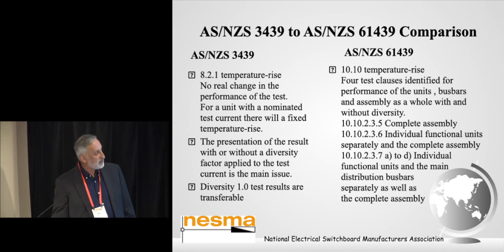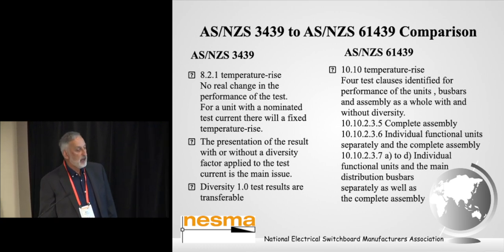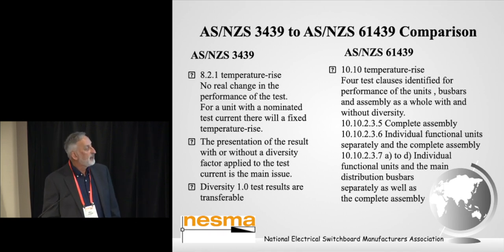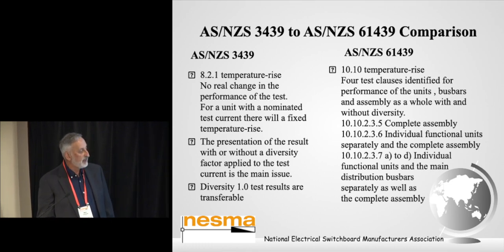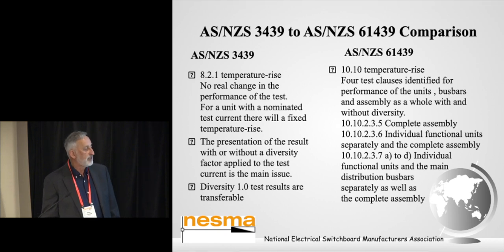But the complication here comes with clause 10.10 for temperature-rise testing. It's been expanded to 4 test clauses identified so you can interrogate the performance of the units, the busbars, the assembly as a whole, with and without diversity. So that's broken down into these sub-clauses: 10.10.2.3.5, which is a temperature-rise test on the entire assembly, and that's where you actually say the 821 test is sort of transferable into that particular clause. The 10.10.2.3.6 and 10.10.2.3.7 break down the test into looking into the performance of individual functional units and the complete assembly, and also looking into the performance of the main bars, the distribution bars, separately, as well as the complete assembly.